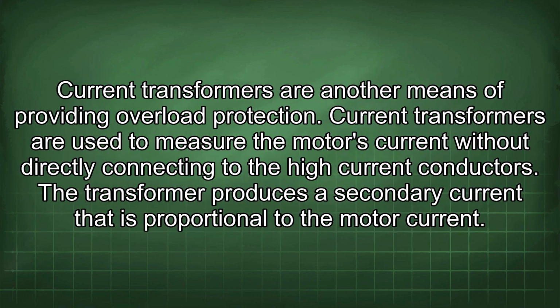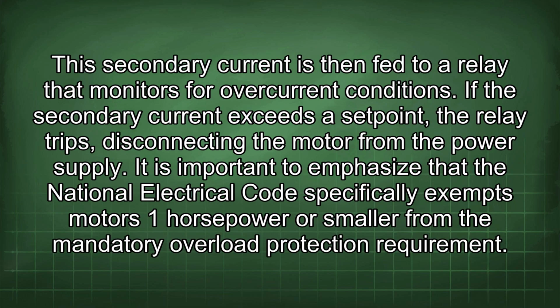Current transformers are another means of providing overload protection. Current transformers are used to measure the motor's current without directly connecting to the high current conductors. The transformer produces a secondary current that is proportional to the motor current. This secondary current is then fed to a relay that monitors for overcurrent conditions. If the secondary current exceeds a set point, the relay trips, disconnecting the motor from the power supply.